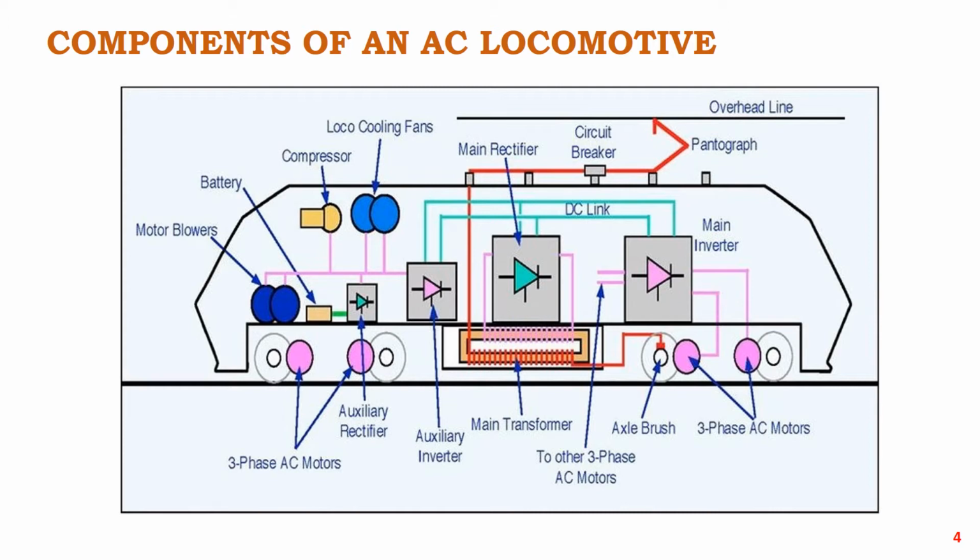First one is transformer. The line voltage has to be stepped down before use on the train. Traction transformers of the trains and railway stock transform the overhead contact line voltage, which ranges mainly from 15 kV or 25 kV, to voltages of 0.7 and 1.5 kV. Normally transformers used are of rating 5600 kVA to 7200 kVA.